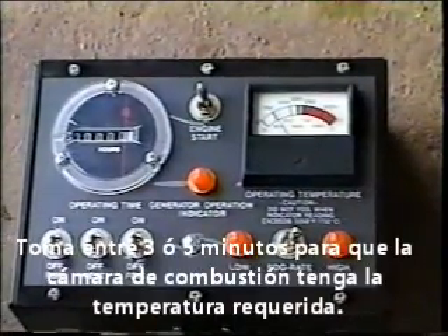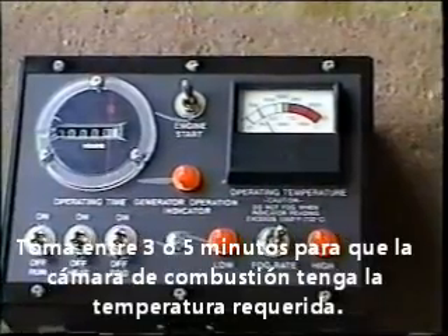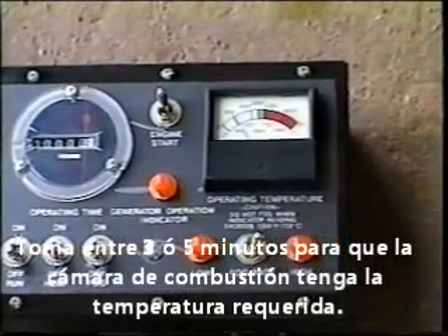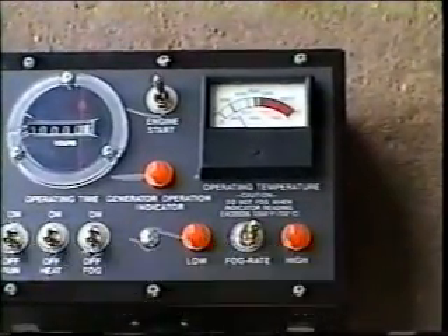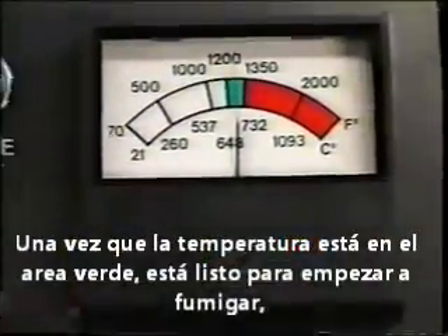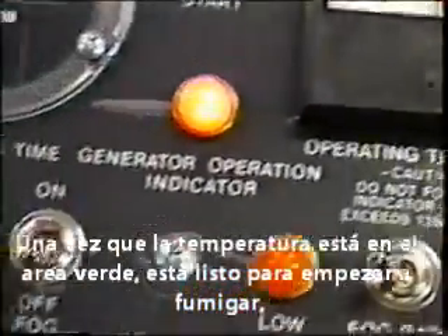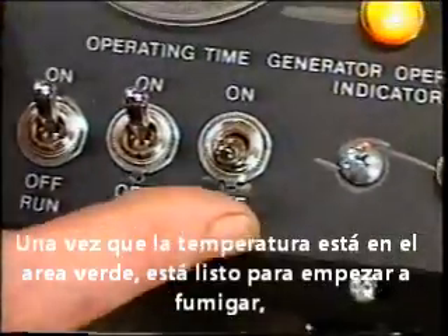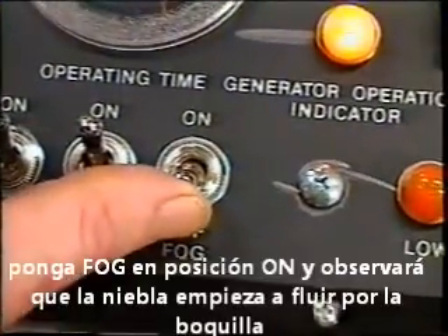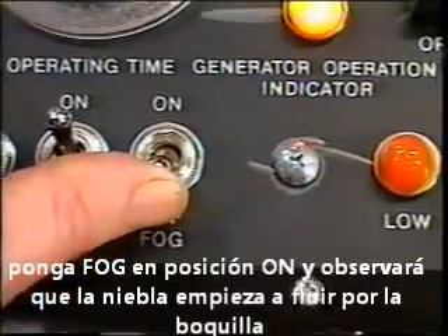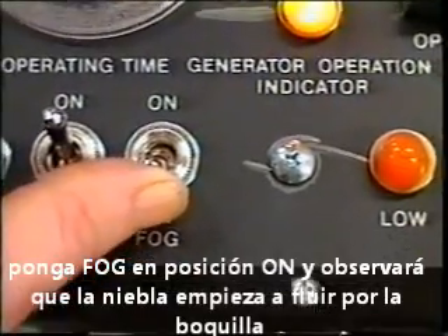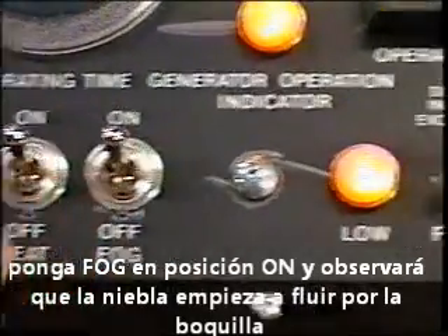It will normally take between 3 and 5 minutes to reach the required temperature of the combustion chamber. Once the temperature is in the green area, you are now ready to begin the fog. By placing the fog into the on position, you will observe that the fog will now begin flowing from the nozzle.